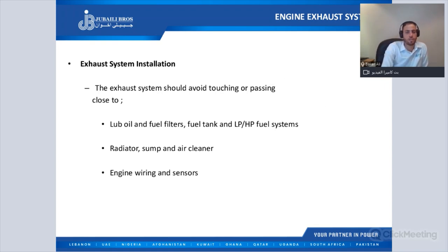The exhaust system should avoid touching or passing close to the oil and fuel filters, fuel tank, low pressure and high pressure fuel systems, radiator, air cleaner, oil sump, and engine wiring and sensors. So we should take care about this. The exhaust system should not touch or pass close to these items.